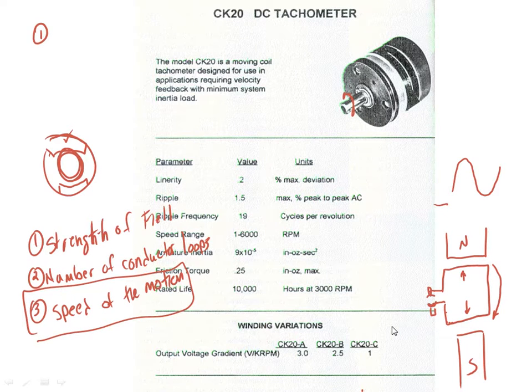You can literally run a DC motor so fast it'll sling itself apart. We had some 200 horsepower motors on the take-up end at the number 4 galvanizing line, and one of them would sling itself apart every once in a while. We had speed sensors with a centrifugal switch that was supposed to cut it off if it ran too fast, plus a tach generator, but for some reason that one would still fly apart.